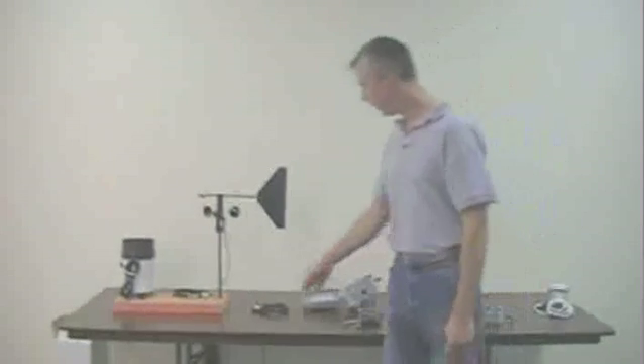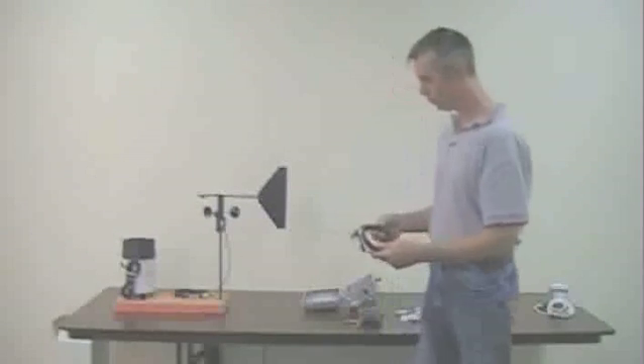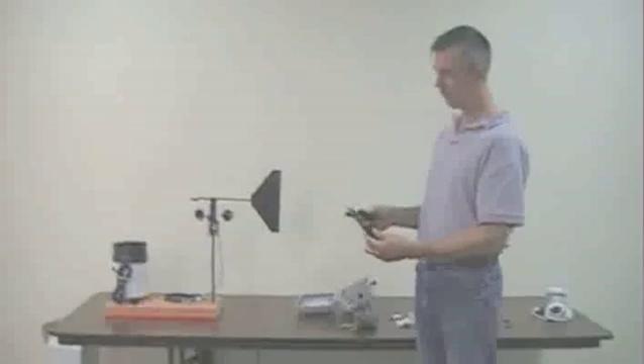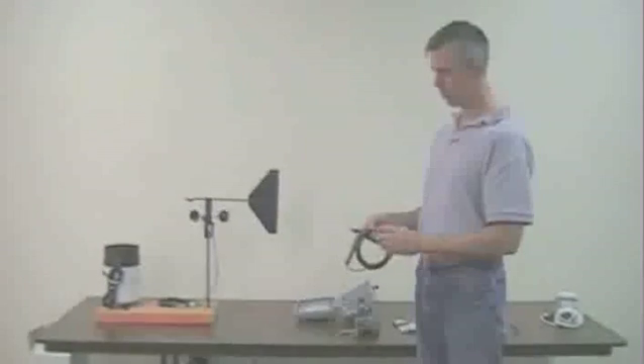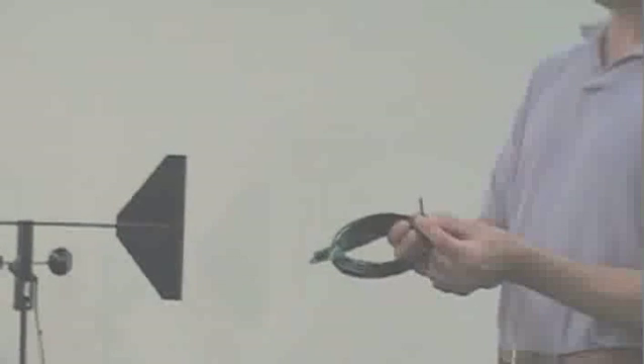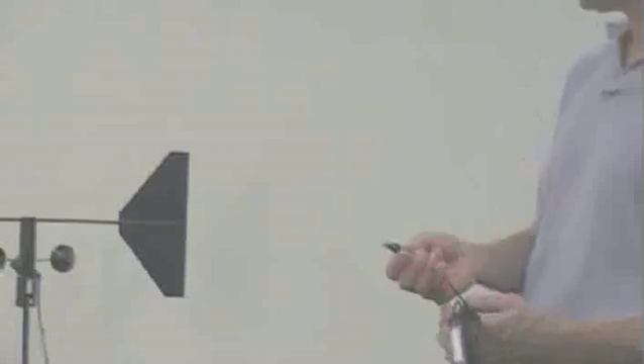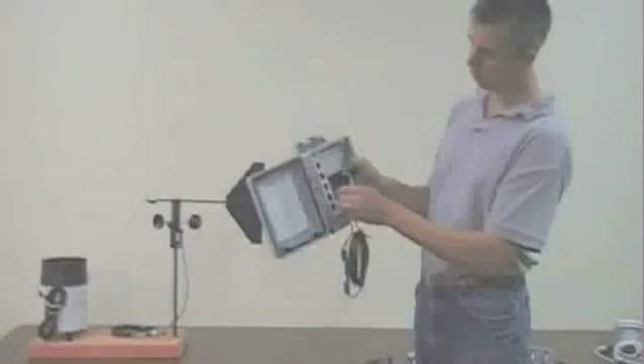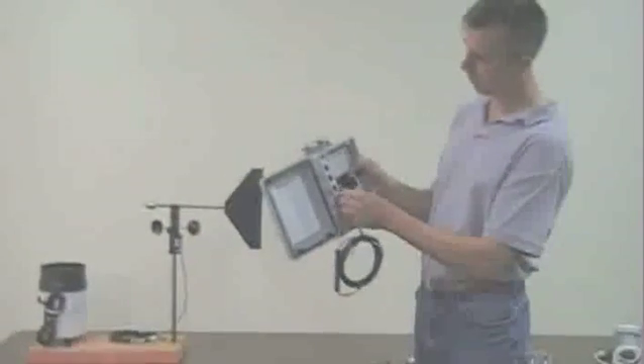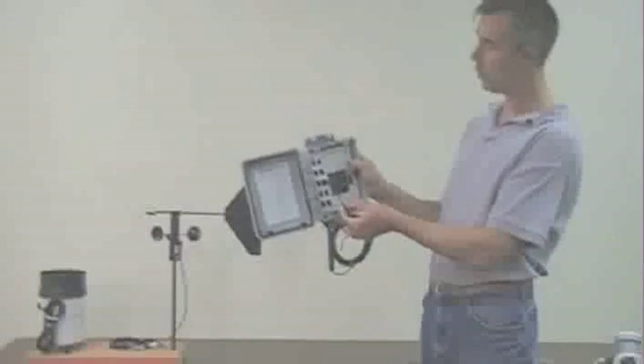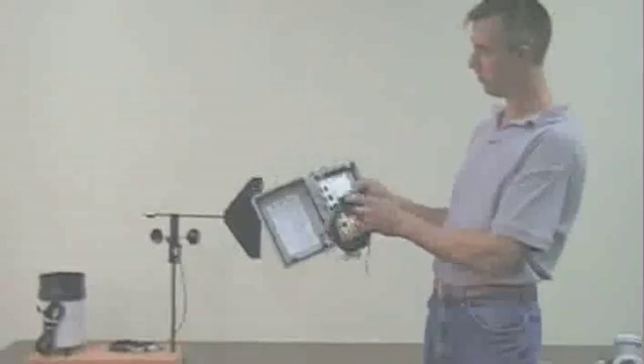The actual sensors. Here we have a temperature sensor. You can see the actual thermistor tip here, protected by the stainless steel housing. And to actually hook this up at this time to the logger, all we simply need to do is plug it in like that, as we'll do with all the rest of the sensors.